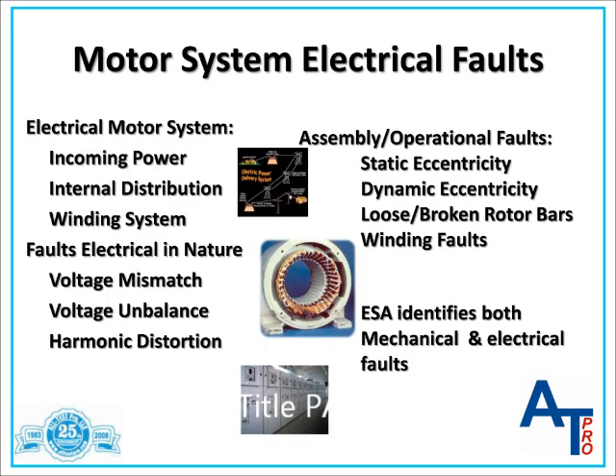The electrical subsystem consists of the incoming power, the internal distribution system, the motor starter, controller, and the motor winding and rotor system. The types of faults that occur in the electrical subsystem are mostly electrical in nature. Incoming faults range from voltage mismatch, unbalance, or non-sinusoidal input. These faults can come directly from the supplier or from faults in the internal transmission or distribution system.